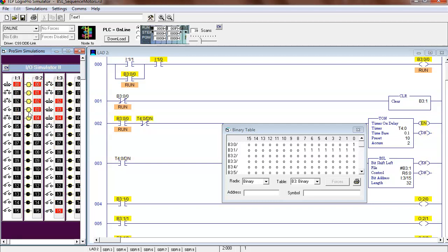We can go ahead and use more outputs. But in fact, instead of doing this, what I could just do is use the move instruction and just move it into an output port, right? Here we're actually using 3 outputs. So this would sequence start a motor. So this would sequence start motors, right? So here I got 5 motors out here, and then I would come up here. Let's stop it.